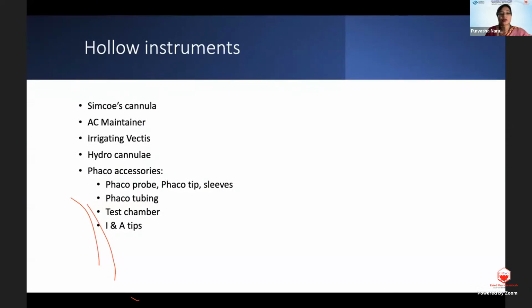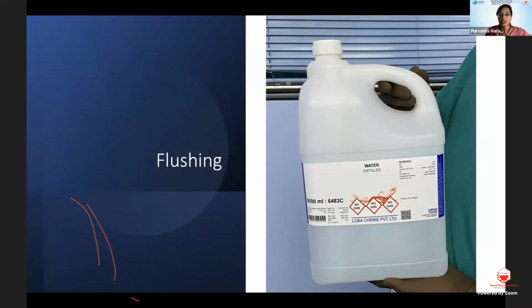For hollow instruments like Simcoe's irrigation aspiration cannula, AC maintainers, or the Blumenthal technique irrigating vectis for nucleus delivery, your hydrocannulae, or for that matter other hollow instruments, you have to first flush them properly. That is done with distilled water, not just tap water, because tap water is usually known to carry endotoxins and other contaminants which have been found. So it's always better to flush with distilled water. Deionized is better. The flushing is done using a 20 cc syringe, and each hollow tube is flushed 2 to 3 times, followed by pushing in air. After the distilled water, 2 to 3 cycles of flushing with air are done, and then the instruments are placed in the tray and passed on.